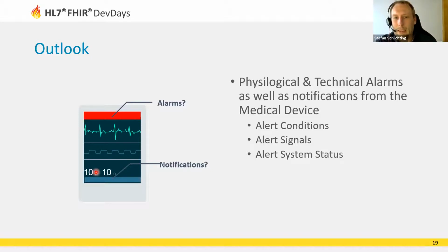If you look at the data models used in the other standards, for example the IEEE 11073 standards as well as the PHD standard, you basically have to distinguish between the alert condition, so basically what is monitored, how it's signaled, so alert signals, and also the alert system status—for example, if someone has turned off the monitoring for something, or maybe just the acoustical alarming.